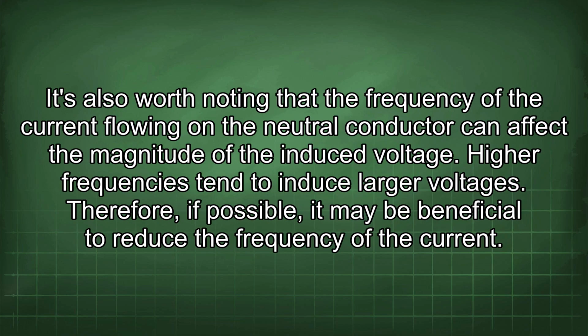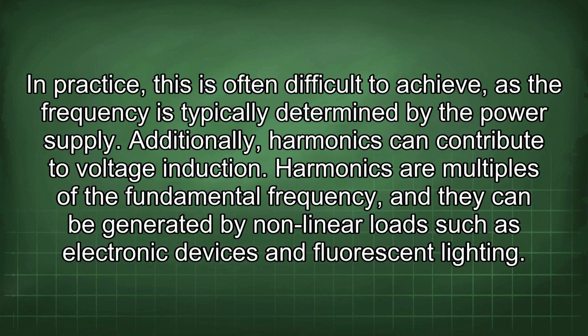It's also worth noting that the frequency of the current flowing on the neutral conductor can affect the magnitude of the induced voltage. Higher frequencies tend to induce larger voltages. Therefore, if possible, it may be beneficial to reduce the frequency of the current. In practice, this is often difficult to achieve, as the frequency is typically determined by the power supply.